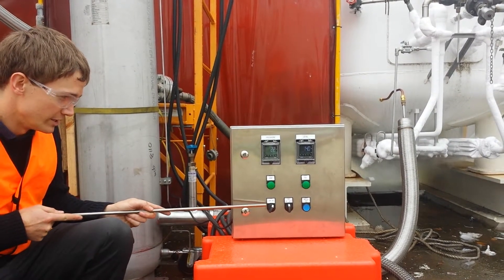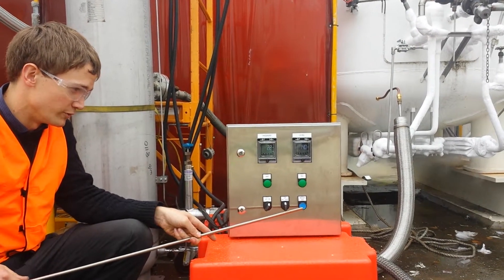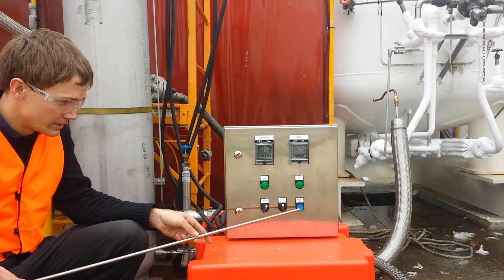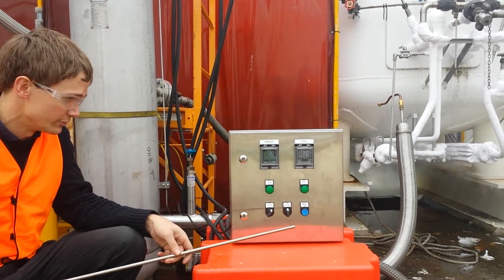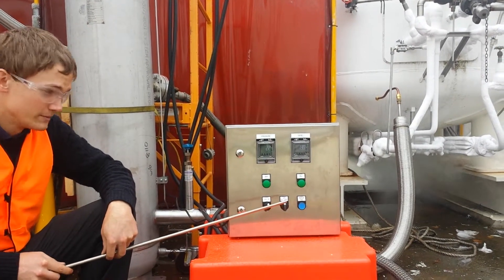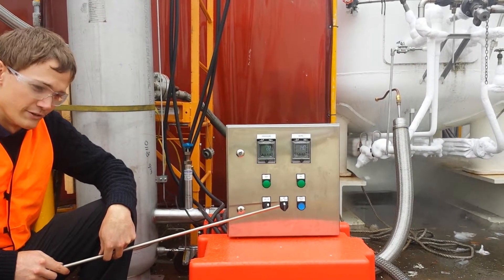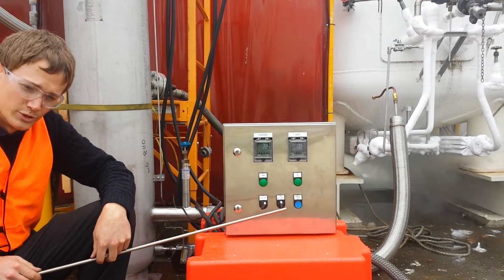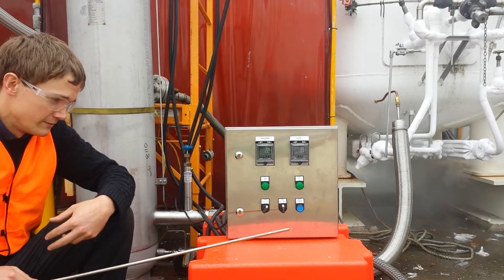We have the on/off switch, which is pretty obvious. We also have a manual vent override, which basically opens the vent solenoid regardless of everything else. And we have our liquid control — currently it's set to off.